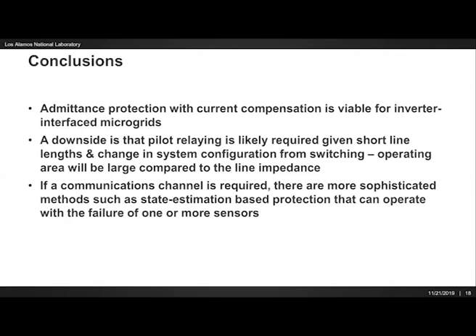Now, given the requirement for a communications channel, this does open the door to more sophisticated protection schemes. So one particular scheme that I've been looking at recently is that of state estimation-based protection, which has been proposed both on the transmission and distribution system. And this is a generalization of differential protection. And it's able to operate with the failure of one or more sensors while still being able to discriminate between in-zone and out-of-zone faults. So that brings me to my conclusion.